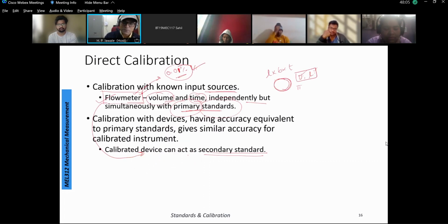The earlier example we have taken, the calibrated device can be used as a secondary calibration. This is indirect calibration now. Indirect calibration of the flow meters used in house, say for example water measurement or something, can be calibrated using the calibrated flow meter. So it is indirect calibration. Direct calibration and indirect calibration. So I think you have got the difference between direct calibration and indirect. Direct calibration is in connection with the primary standards, something that I am calibrating using very established primary standards. That is called direct calibration.